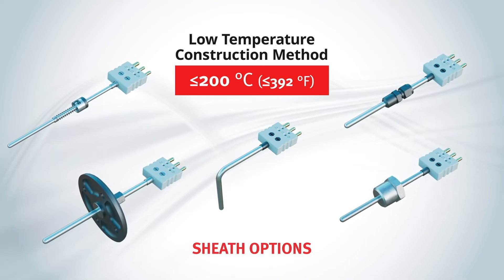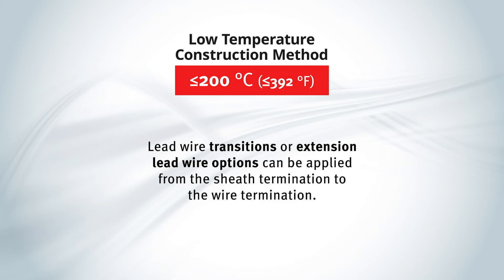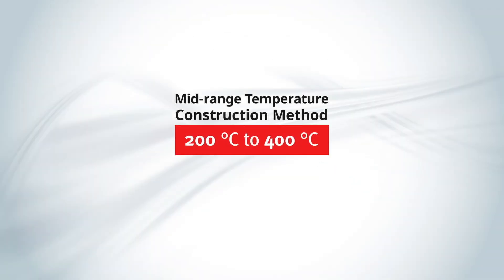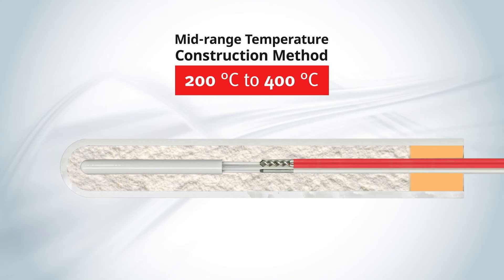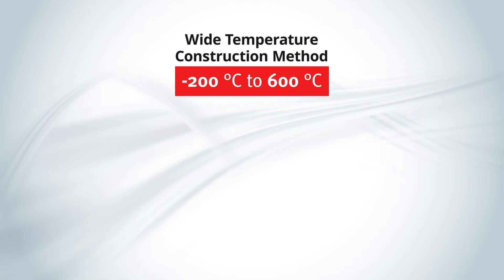Lead wire transitions or extension lead wire options can be applied from the sheath termination to the wire termination. A variety of lead wire termination options can be used. If the application calls for measuring temperatures in the mid-range between 200 degrees Celsius to 400 degrees Celsius, a similar construction can be used. However, the lead wire insulation is changed to fiberglass or polyimide, depending on the specific range. Wider temperature ranges — those between minus 200 degrees Celsius and 600 degrees Celsius — may require a different assembly construction.